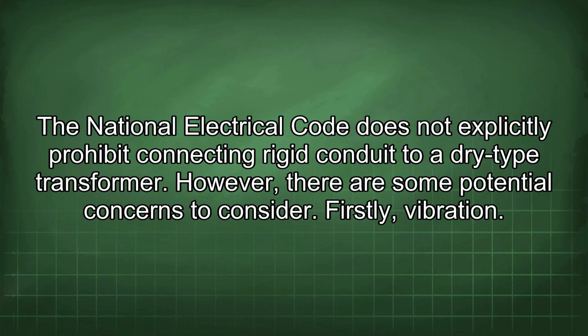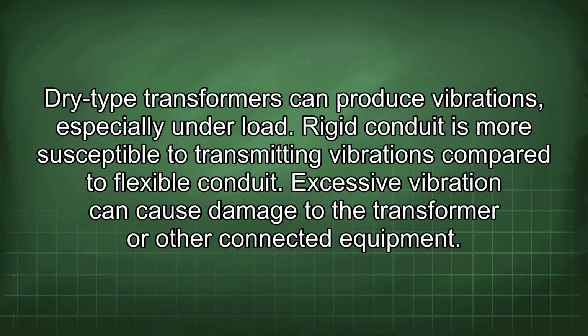The National Electrical Code does not explicitly prohibit connecting rigid conduit to a dry-type transformer. However, there are some potential concerns to consider. Firstly, vibration. Dry-type transformers can produce vibrations, especially under load. Rigid conduit is more susceptible to transmitting vibrations compared to flexible conduit. Excessive vibration can cause damage to the transformer or other connected equipment.